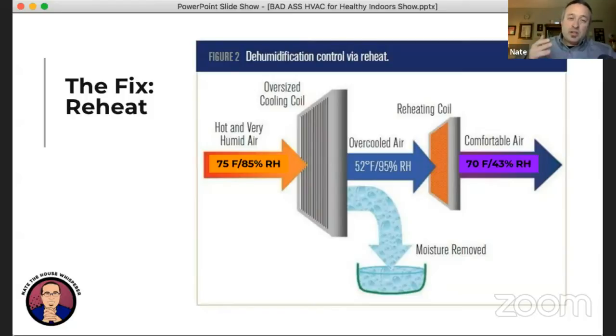The challenging condition that almost every climate has 3 months or so a year is when it's 70 or 75 degrees outside, but the dew point is pushing 70 as well. So there's almost no cooling load, but there's a whole lot of dehumidification that needs to get done. And if you don't address that...